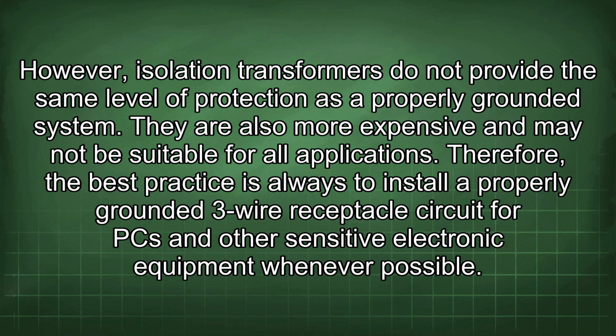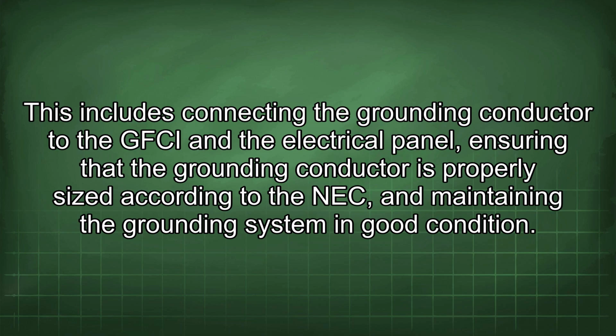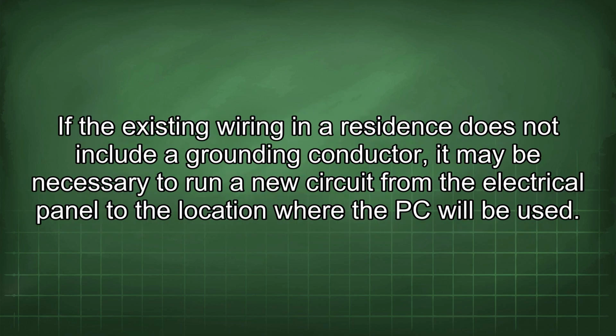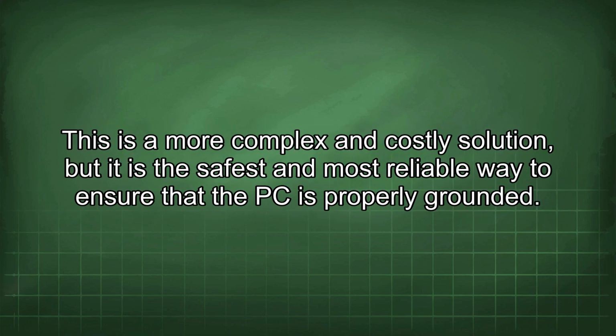Therefore, the best practice is always to install a properly grounded 3-wire receptacle circuit for PC and other sensitive electronic equipment whenever possible. This includes connecting the grounding conductor to the GFCI and the electrical panel, ensuring that the grounding conductor is properly sized according to the NEC, and maintaining the grounding system in good condition. If the existing wiring in a residence does not include a grounding conductor, it may be necessary to run a new circuit from the electrical panel to the location where the PC will be used. This is a more complex and costly solution, but it is the safest and most reliable way to ensure that the PC is properly grounded.